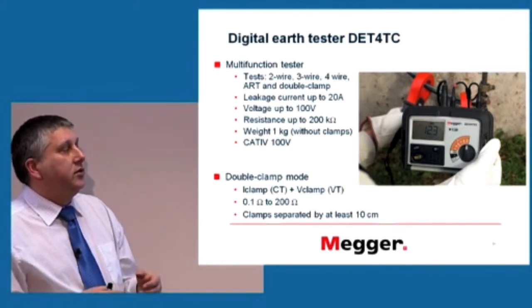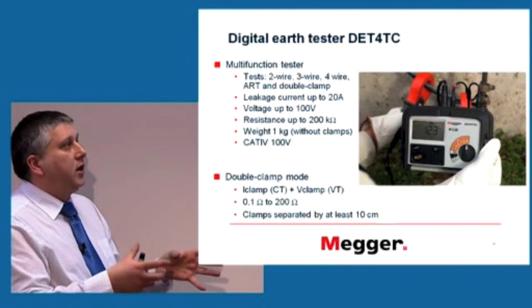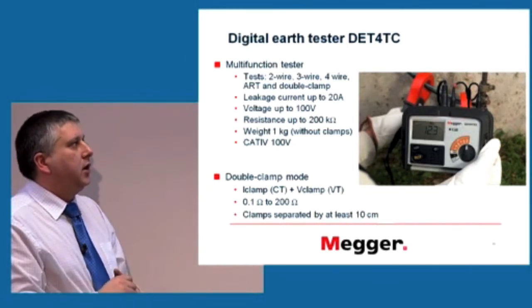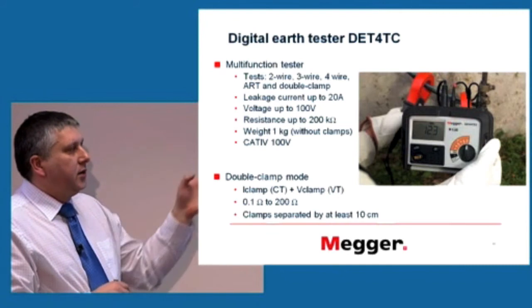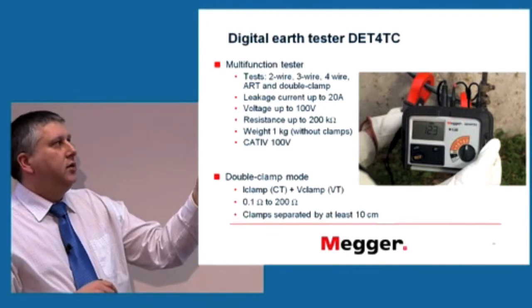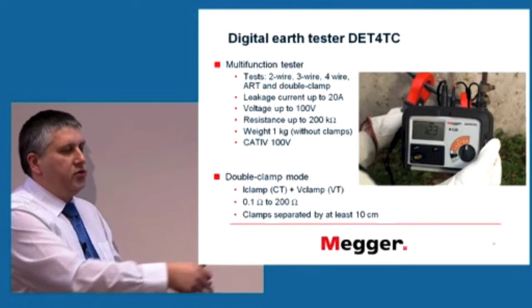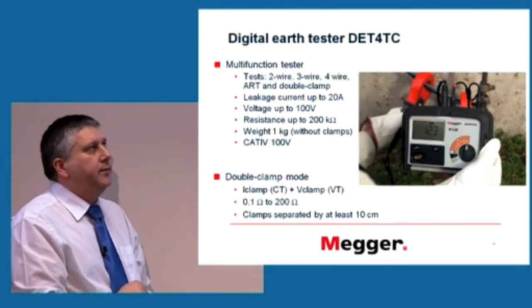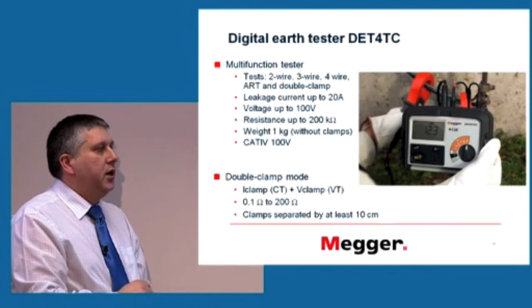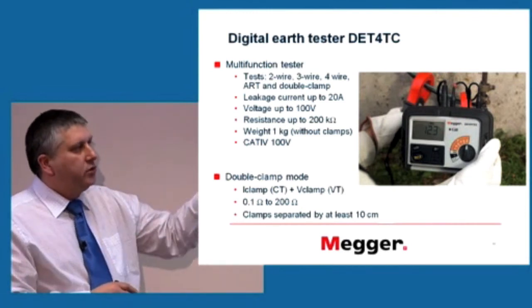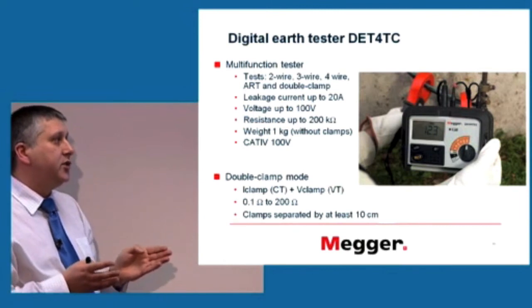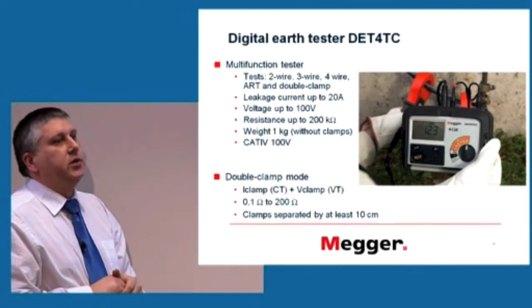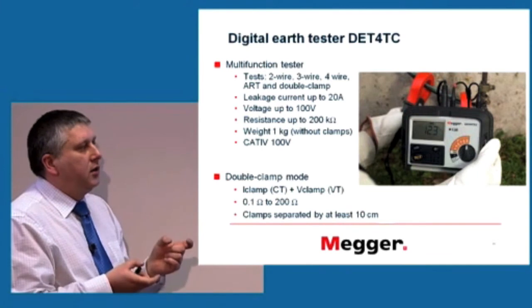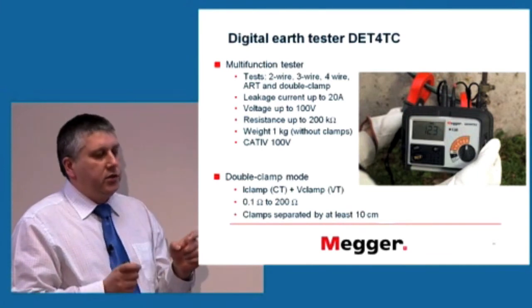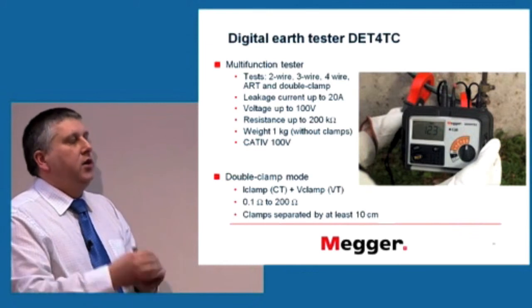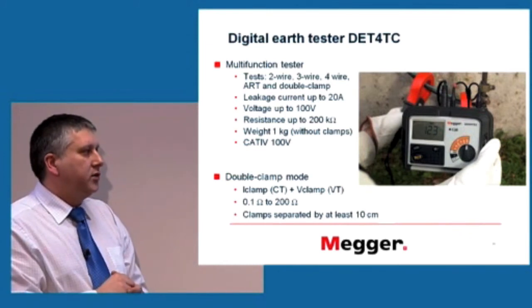It can measure resistance up to 200 kilo ohms. It weighs about 1 kilo, just the device without the clamps. Clamps are a bit heavy as well. And this one is category IV 100 volts. So we cannot connect this instrument straight to our power socket because it is not designed to work with these sorts of voltages. In double clamp mode, we use two transformers, which are basically exactly the same. It can measure up to 200 ohms, because that method is only a sort of approximation. You cannot achieve as good accuracy as with the other methods.